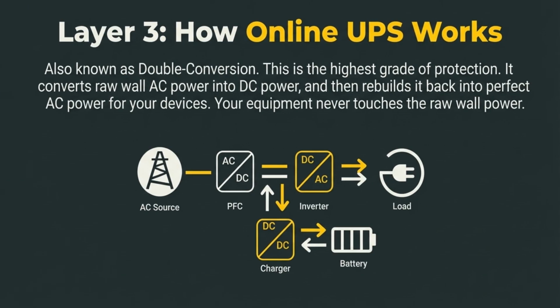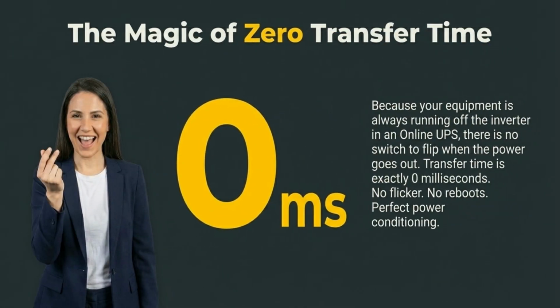Layer 3 is the online UPS, also known as double conversion. This is the highest grade of protection. It converts raw AC power to DC and then rebuilds it into perfect AC power. Your equipment never touches the raw wall power. Because your equipment is always running off the inverter in an online UPS, the transfer time is exactly 0 milliseconds. This means no flicker, no reboots, and perfect power conditioning.